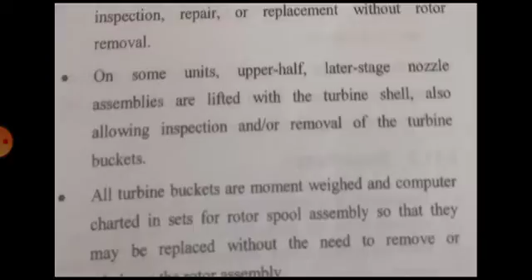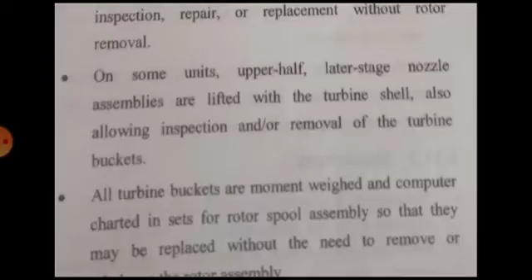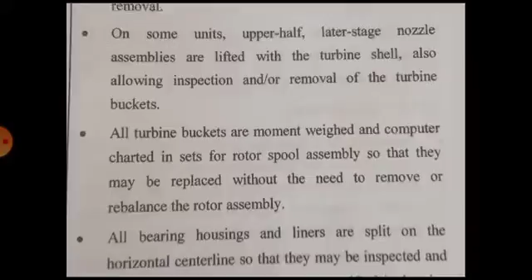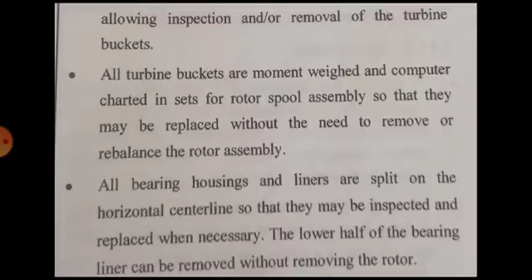All turbine buckets are moment weighed and computer charted in sets for rotor spool assembly so that they may be replaced without the need to remove or rebalance the rotor. All bearing housings and liners are split on the horizontal center line so that they may be inspected and replaced when necessary. The lower half of the bearing liner can be removed without removing the rotor.